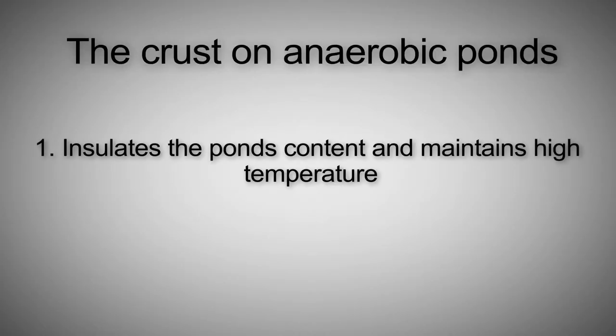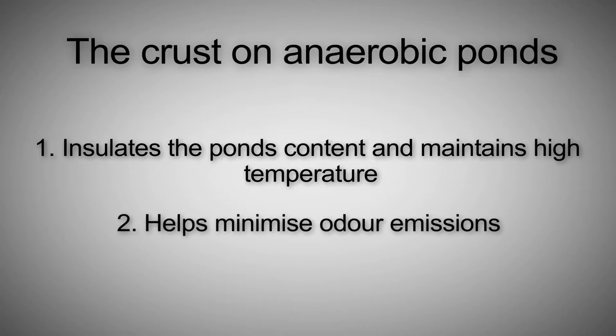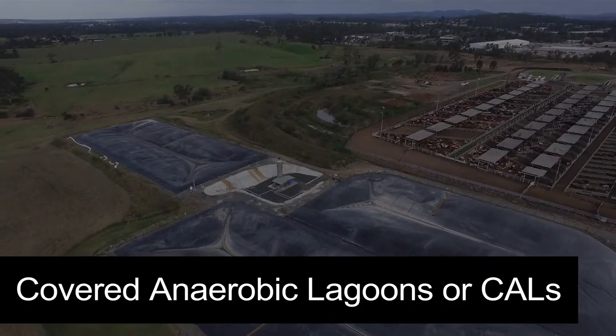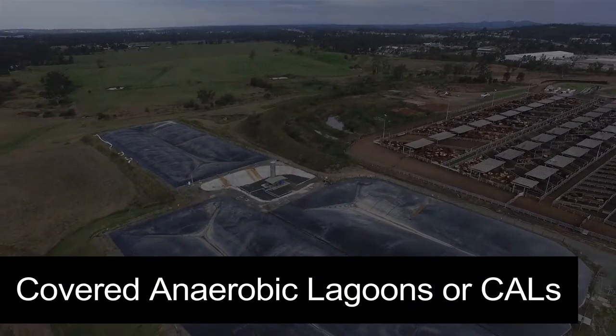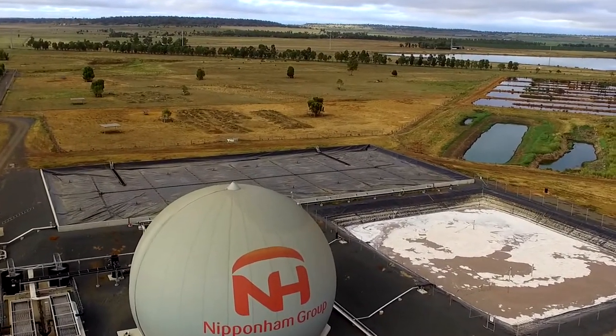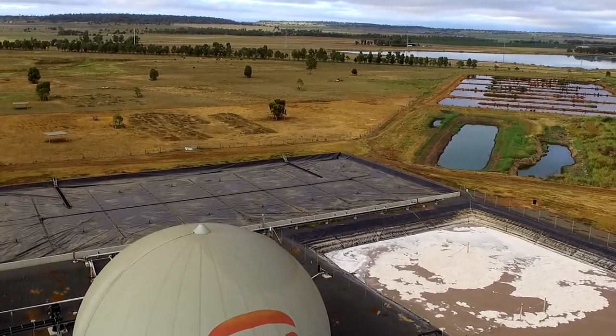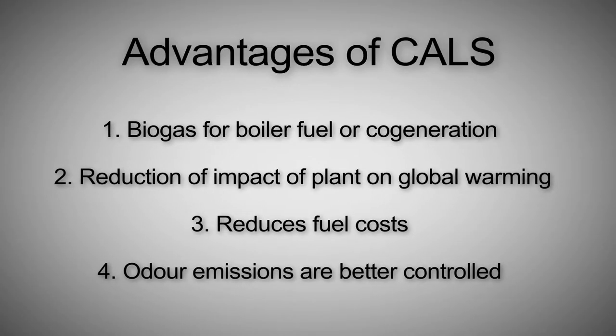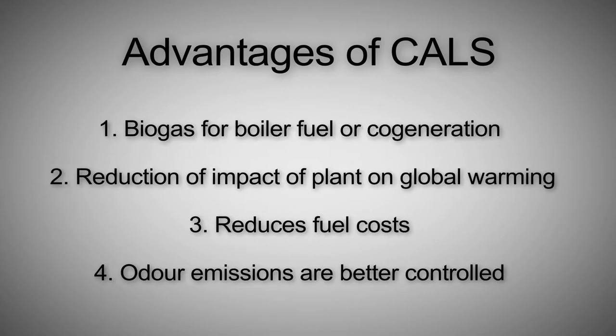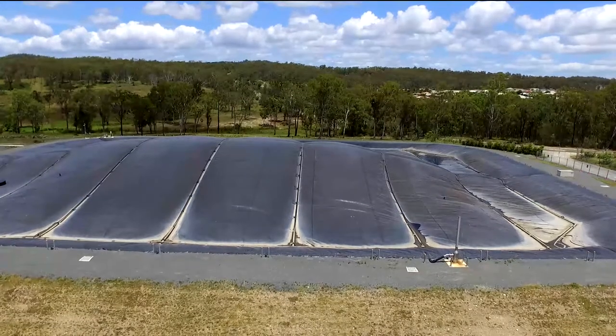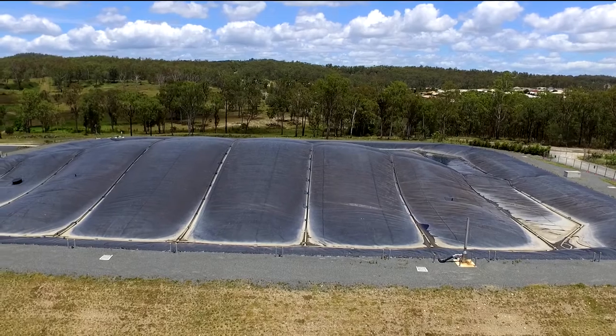This natural crust is considered to play a positive role for the pond in that it insulates the pond contents and helps maintain the pond at high temperatures during cold winter months, helps minimise odour emissions off the pond and minimises oxygen entry into the pond through the water surface. Over the last decade, anaerobic ponds have been designed with a synthetic geomembrane, which seals the pond from the atmosphere and allows the capture of the biogas. The main advantage of covered anaerobic lagoon systems is that while the cover makes little difference to the treatment performance of the pond, biogas can be captured either for flaring or for other uses such as cogeneration or boiler fuel. This reduces the meat processing plant's impact on global warming, reduces fuel costs and odour emissions are better controlled. The downside is their greater cost, usually about double that of naturally crusted ponds.